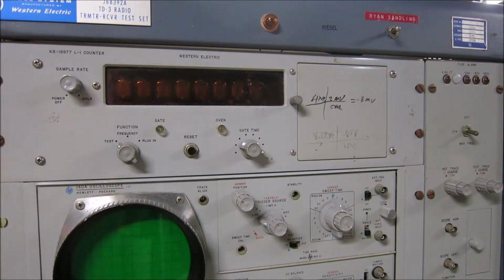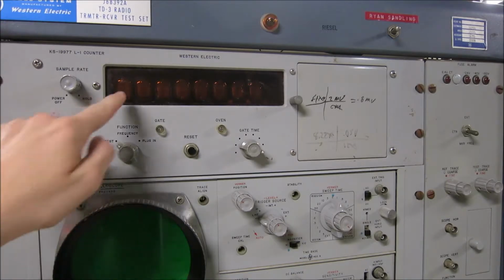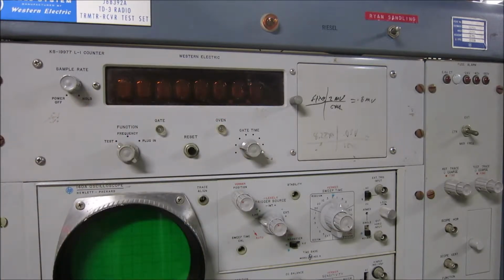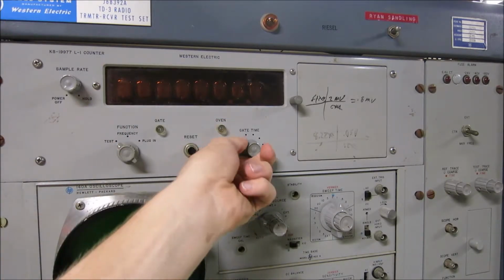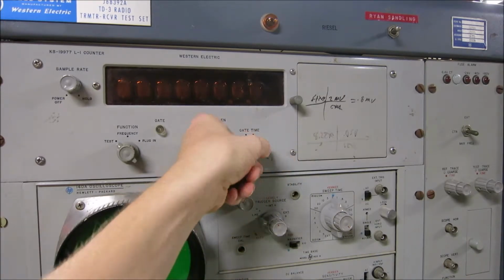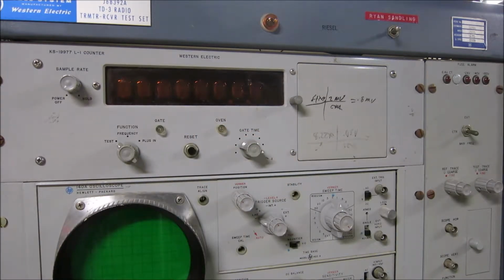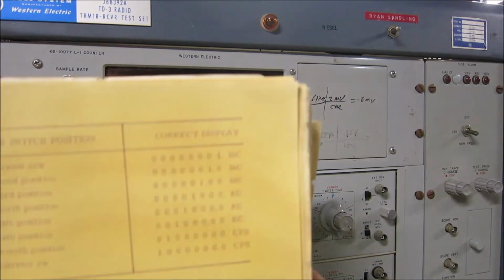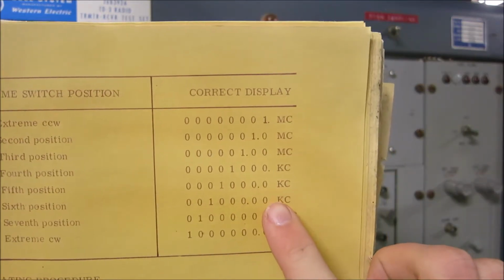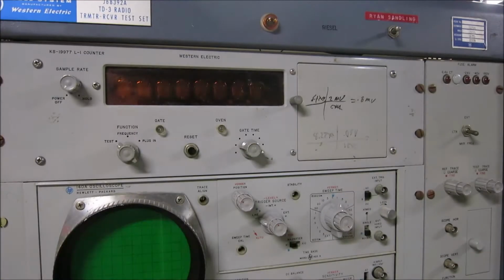This machine contains a built-in crystal oscillator that will send a signal to the analyzer. If that signal is the same throughout the gate time, that means this machine is working properly. As specified by the manual, these are the values that we should receive on the display when the machine is functioning.